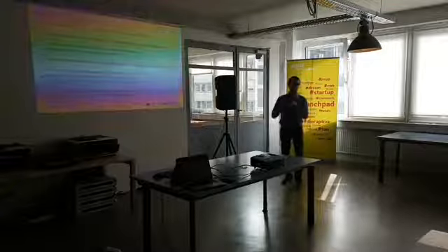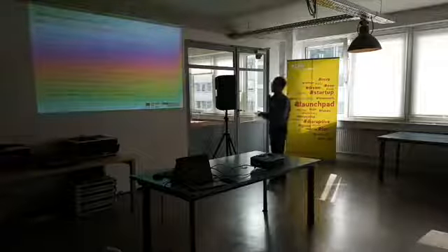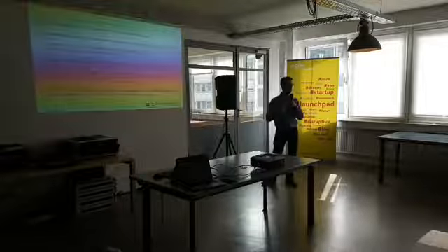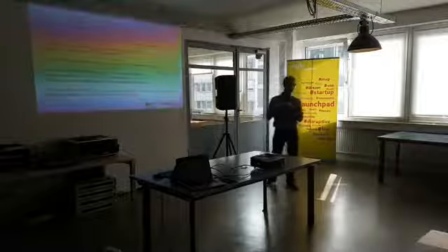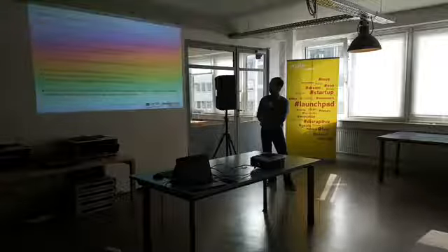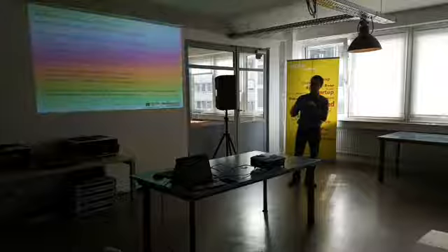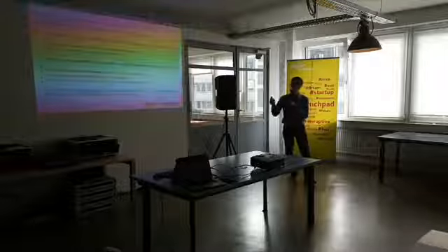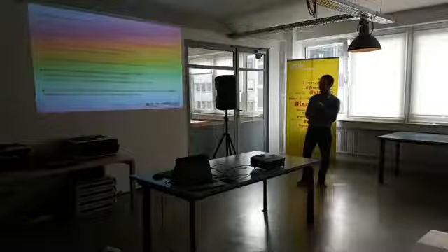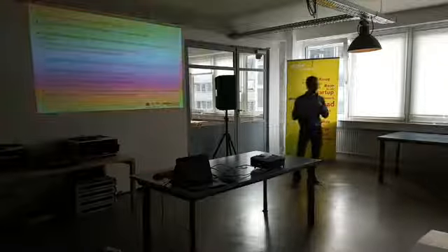Then we look a little at how we integrated the PMU in the architecture. Here I'm speaking in particular about the RWTH side. We have sensors in medium voltage and low voltage that convert the input quantity to a quantity manageable by the PMU, plus or minus 1 volt. Then the PMUs continuously send their calculated values, are connected to GPS, and send values via the 61850 sampled value protocol. The phasor data concentrator subscribes to this measurement. We continuously read them and save them in a database. After that, an application running, in this case in Python, extracts the values every second, because we publish every second. So every second we have updated data, calculate the state estimation, and store it in the database. Finally, we have an application to show the result, so we can see in real time how the state of the grid is evolving.